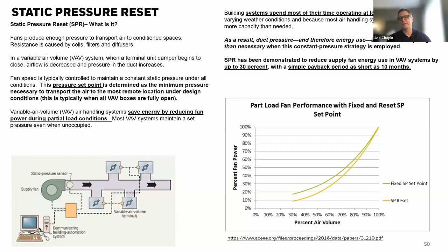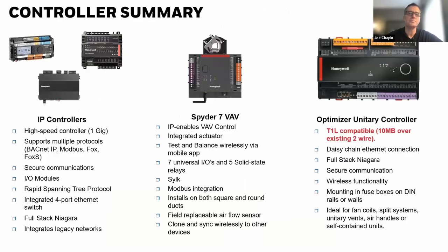And so instead of guesswork, I can say I want my static pressure to be X, and it resets that and it adjusts the VAV boxes to make sure the pressure is working in the most optimal way. Again, it could translate to energy savings with static pressure reset. Just a couple of examples.